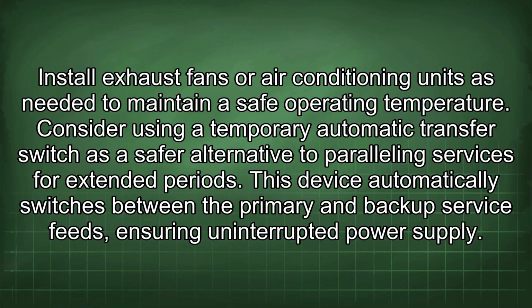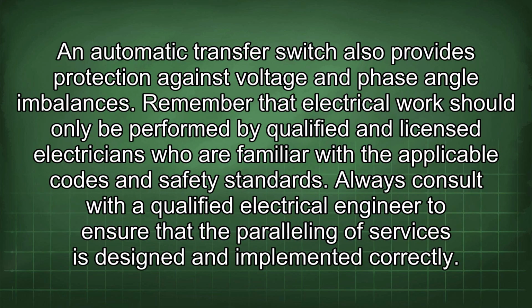Consider using a temporary automatic transfer switch as a safer alternative to paralleling services for extended periods. This device automatically switches between the primary and backup service feeds, ensuring uninterrupted power supply. An automatic transfer switch also provides protection against voltage and phase angle imbalances.